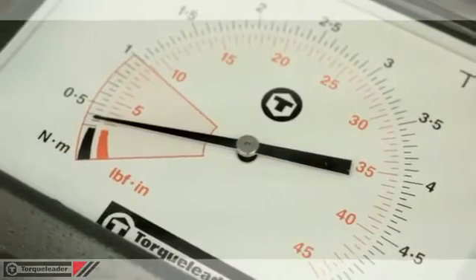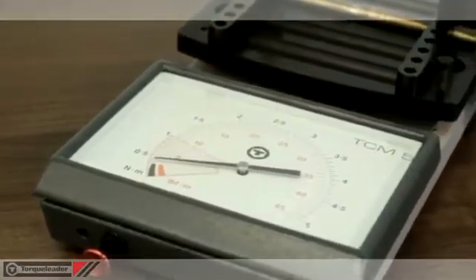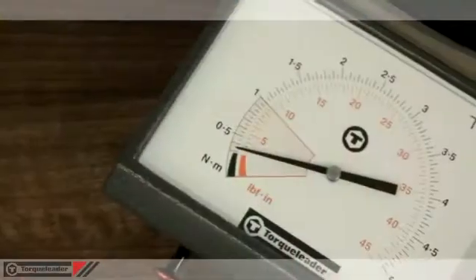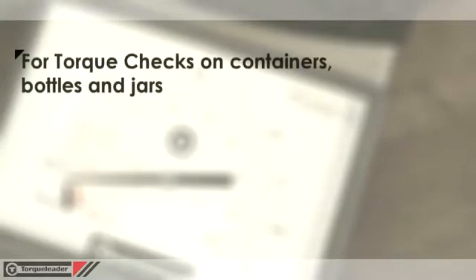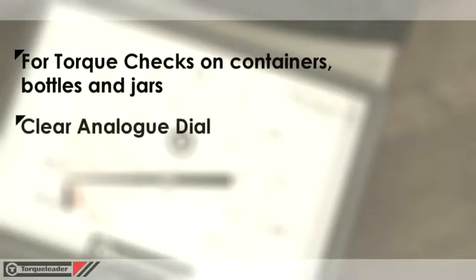This video shows the Torque Leader TCM range of torque closure meters. These are specifically designed to accurately measure the tightness of threaded caps on containers, bottles, and jars. All models feature a large analog dial with both metric and imperial units of measurement.